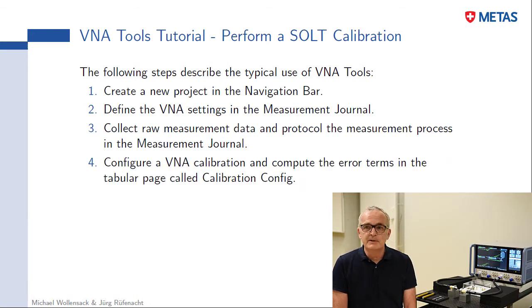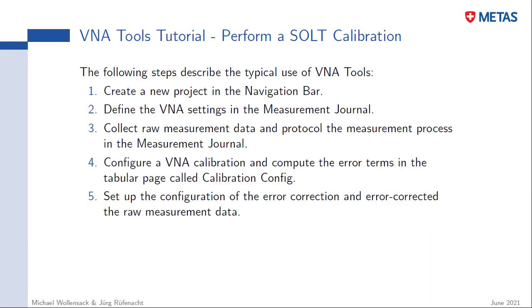Fourth step, configure a Vna calibration and compute the error terms in the tabular page called calibration config. Fifth step, set up the configuration of the error correction and error correct all raw measurement data.